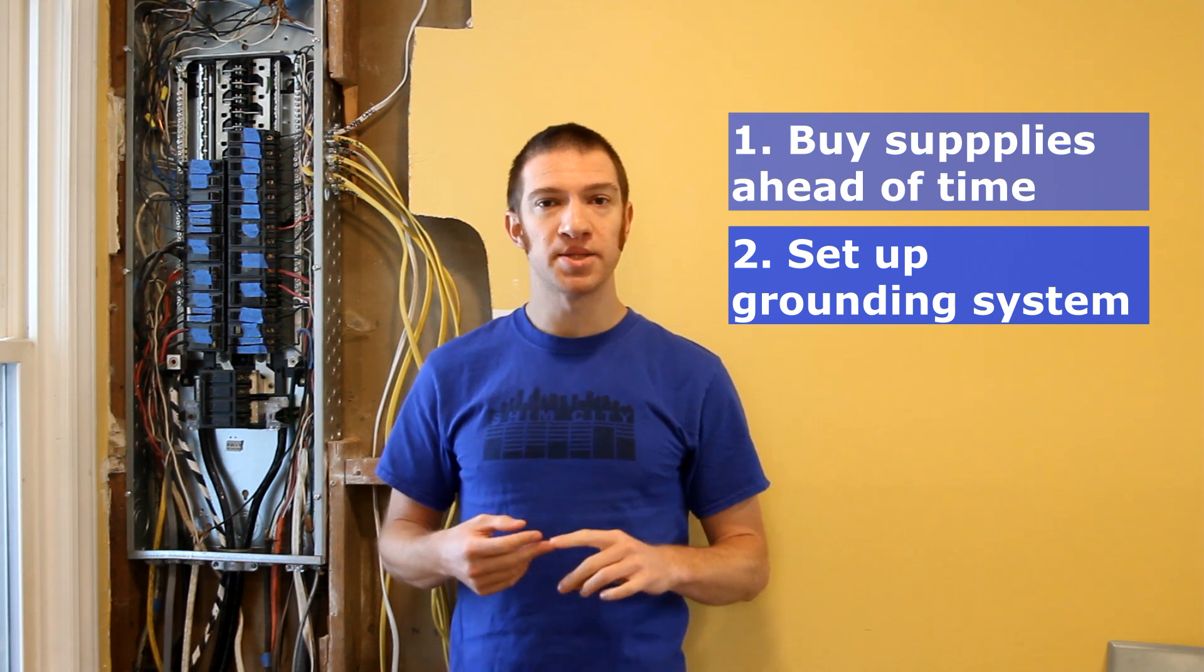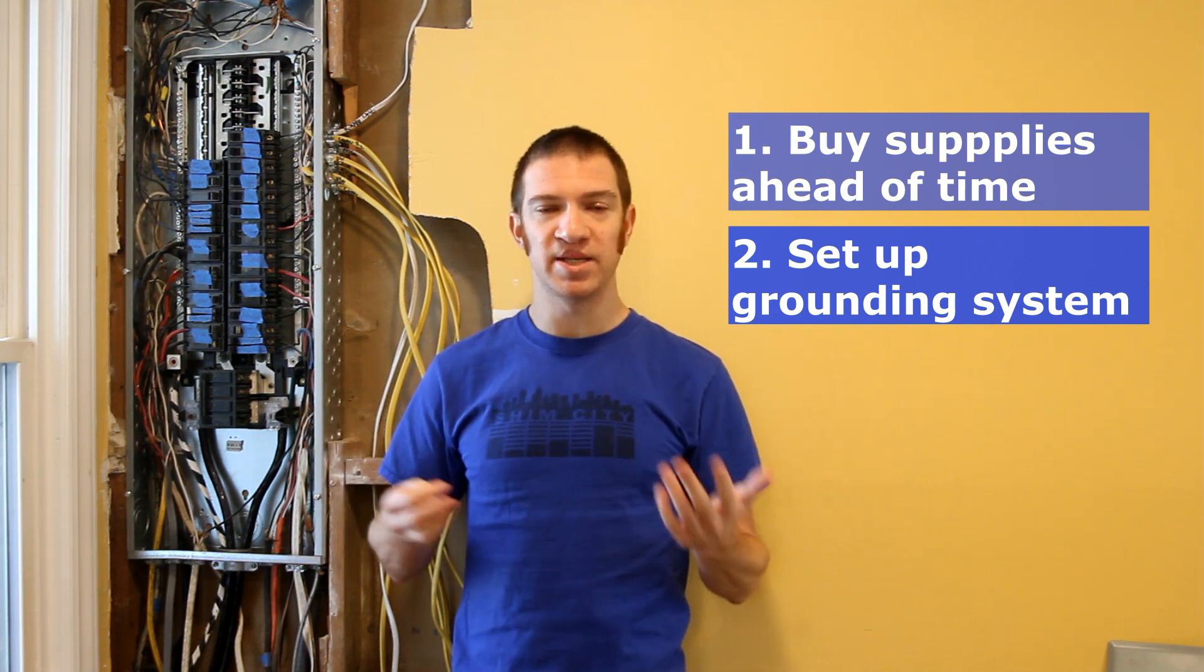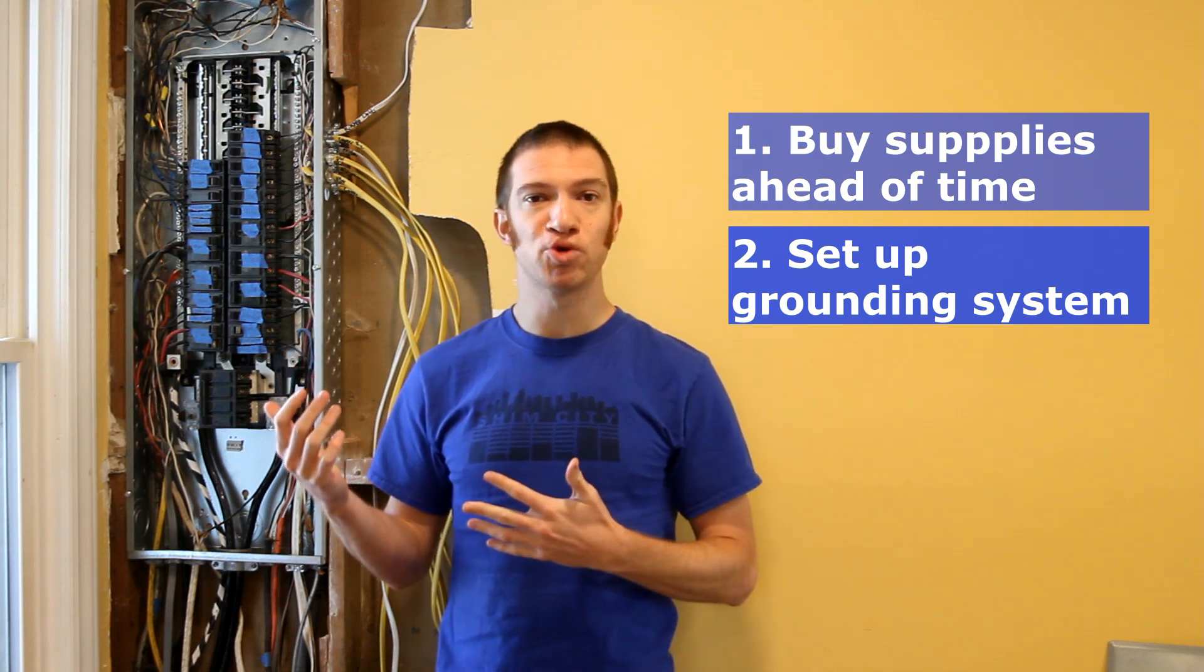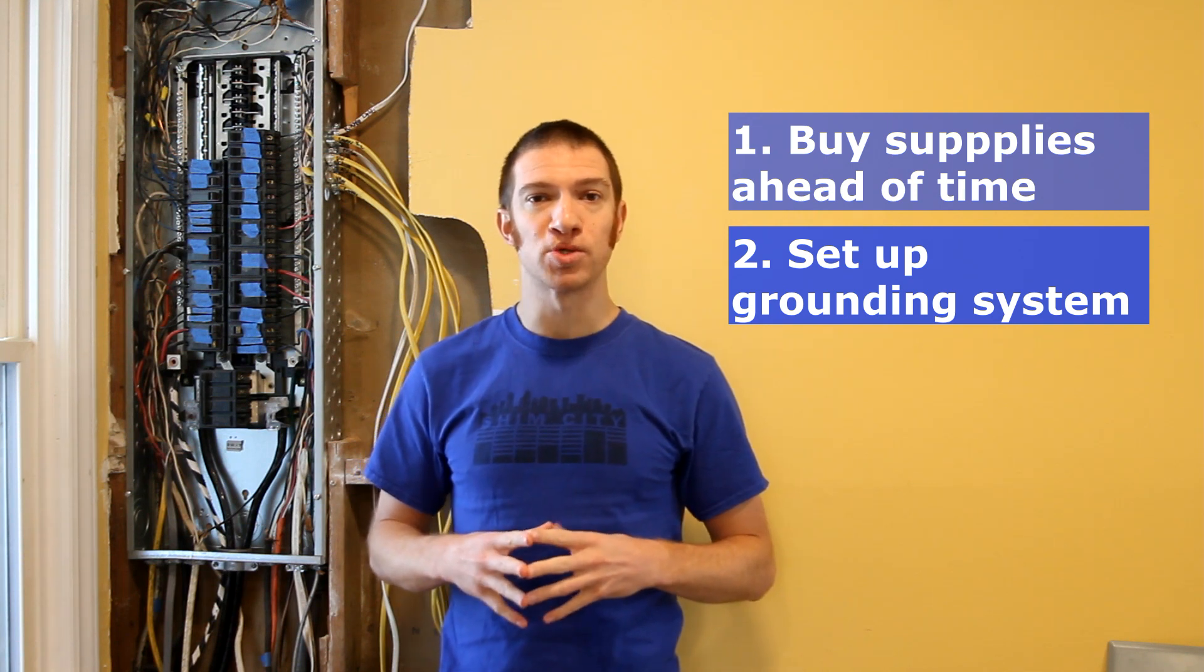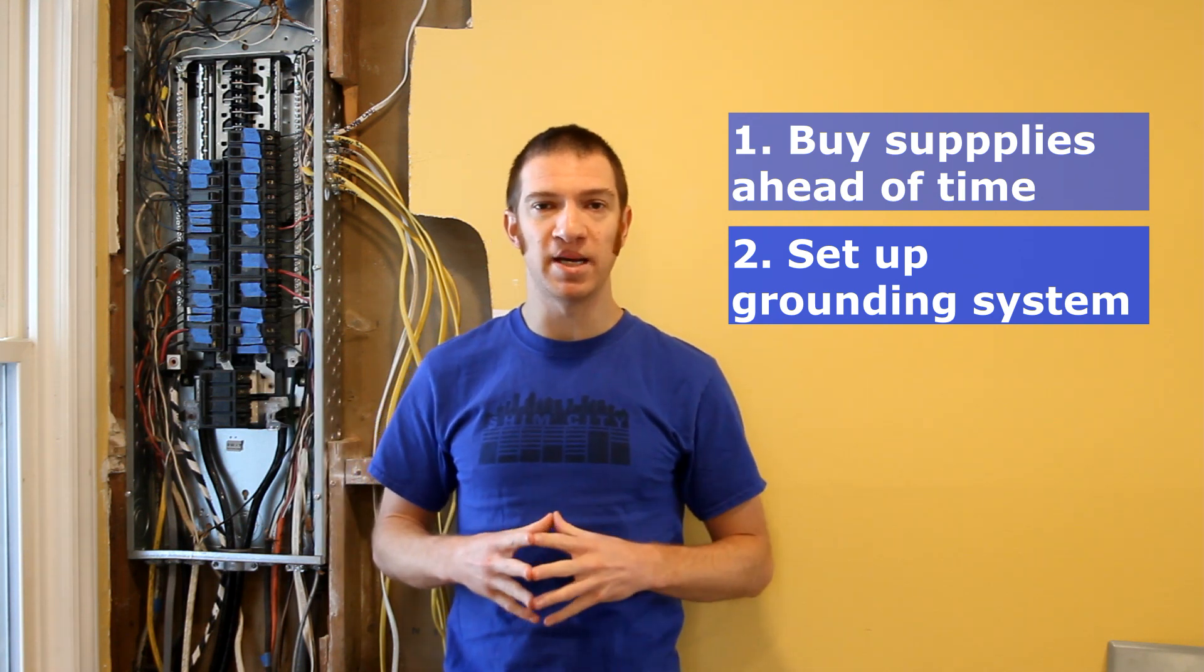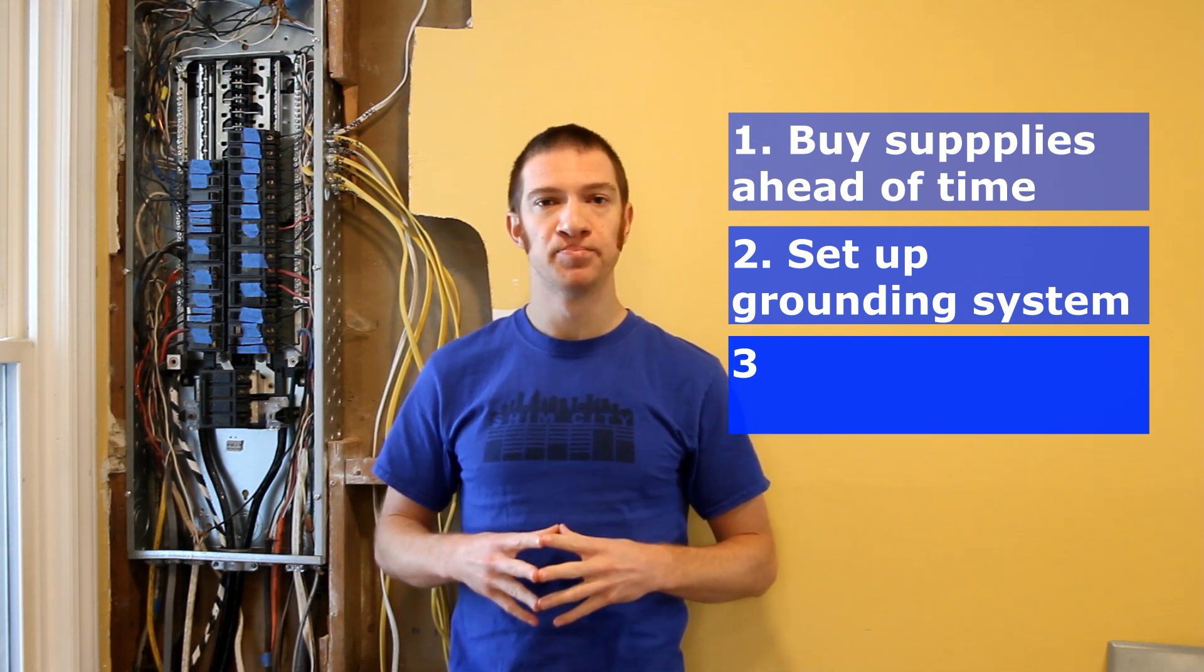The second thing you can do is go ahead and set up your grounding system. Our house was originally built back in the 60s, so they had different grounding systems back then. We actually had to install some new grounding rods and then make sure that all the metal pipes in your house are grounded. So if you have copper pipes, galvanized steel pipes, make sure those are all attached to your grounding system.